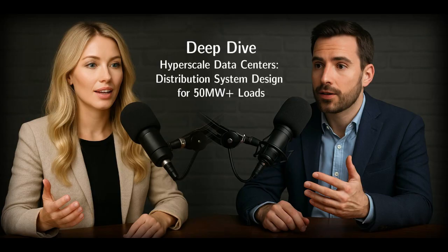And you mentioned fault current contribution earlier. How does that play into protection specifically? Right. Unlike factories with big motors, data centers, being mostly electronic loads, don't contribute much current back into the grid during a fault. This can make it harder for utility relays to reliably detect faults, especially those further out on the system or high impedance faults. It affects sensitivity. So engineers need to use solutions like larger ratio current transformers to see smaller currents, maybe modify the standard time current curves for better coordination, use pilot protection schemes that compare currents at both ends of a line, and perform really detailed short-circuit studies covering all possible operating conditions.